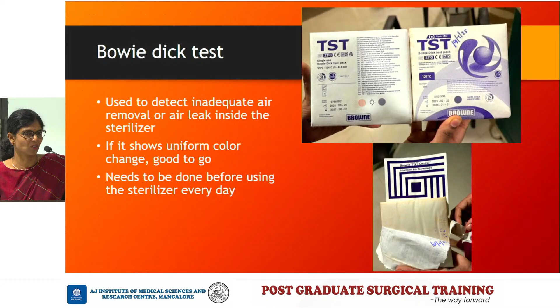This ideally needs to be done before using the sterilizer every day, but generally not done. Usually the Bowie-Dick test is done weekly once. Coming to chemical indicators. Now this is what you generally see on the bins. So the chemical indicators are of 5 classes, but what we generally use are the class 1 and the class 5 indicators. Now class 1 is a process indicator.